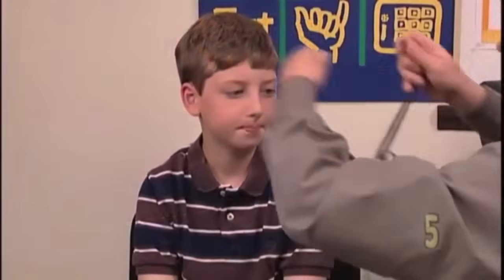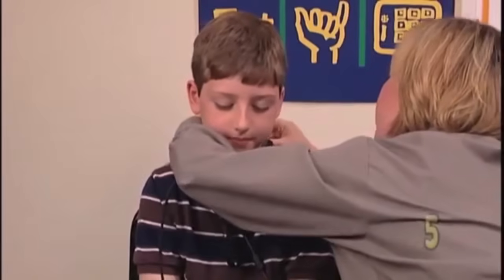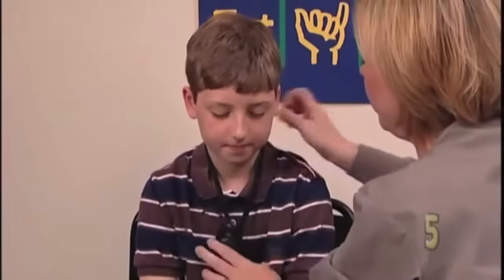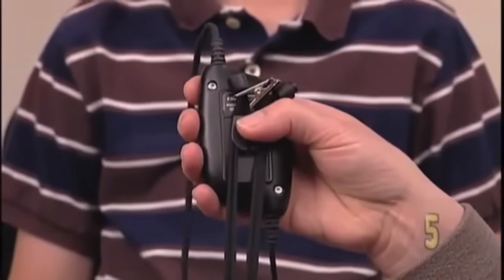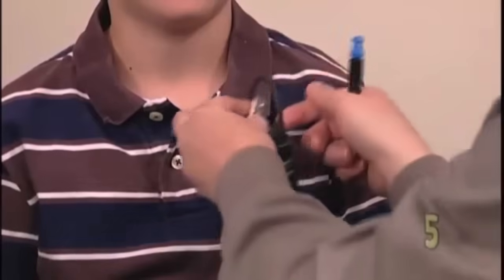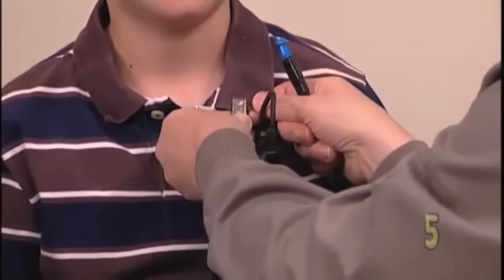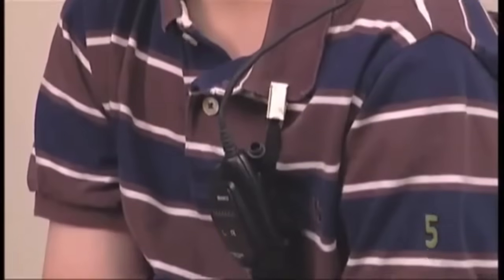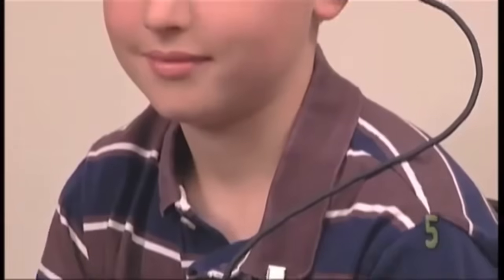Prepare the patient for testing by having them sit in a comfortable position in a quiet area. This step is necessary because environmental or patient noise can cause a test to refer. Then secure the external probe to the patient by using the attached lanyard as a neck loop or by cinching it up and then using the shirt clip to attach it to the patient's collar or other article of clothing. Be sure to have the probe housing close enough to the patient's ear so that the housing does not pull on the probe tip.